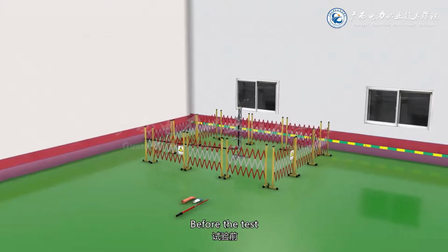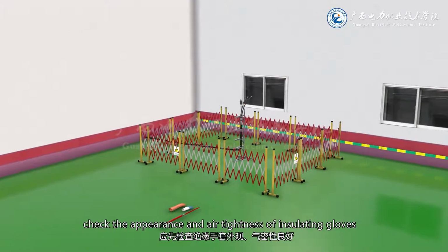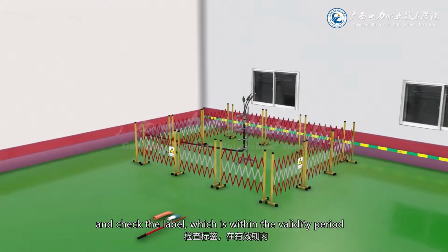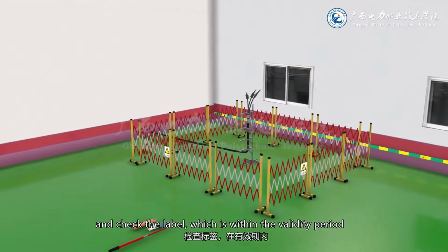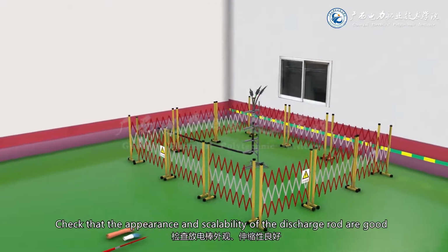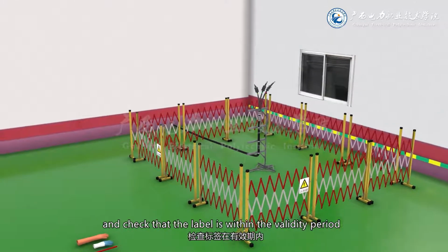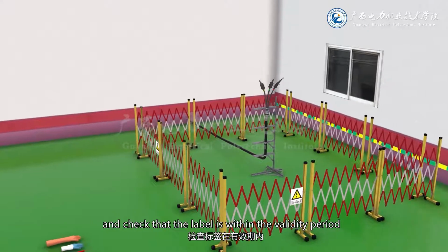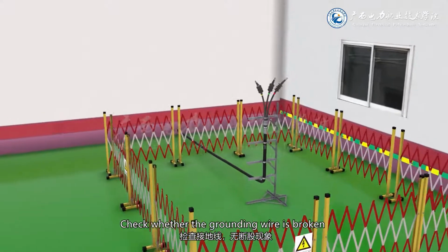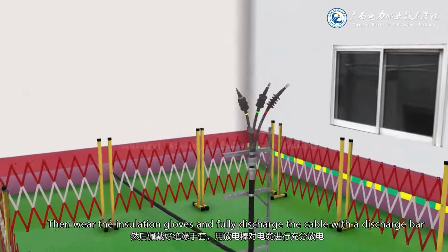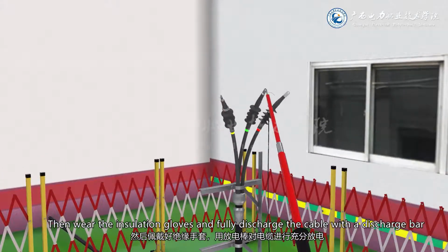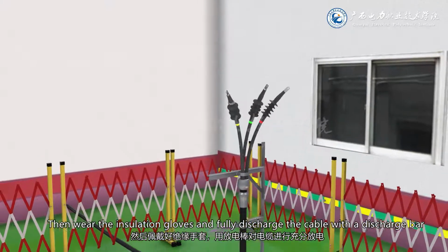Before the test, check the appearance and air tightness of the insulating gloves, and check that the label is within the validity period. Check that the appearance and extensibility of the discharge rod are good, and that the label is within the validity period. Check whether the grounding wire is broken. Then wear insulating gloves and fully discharge the cable with the discharge rod.